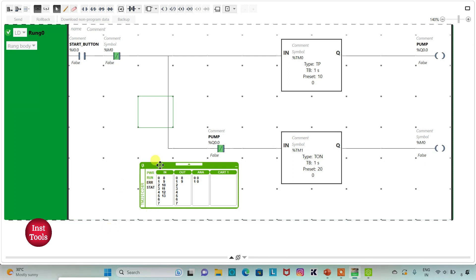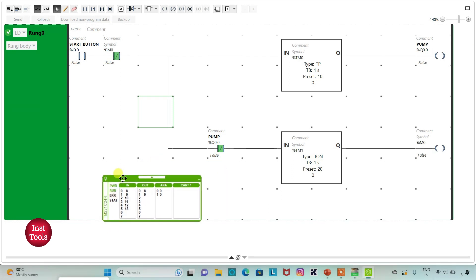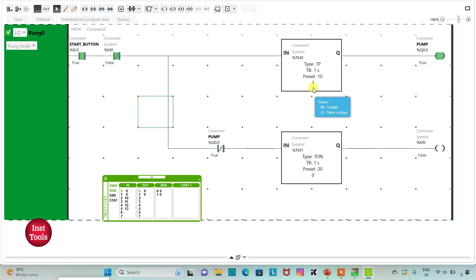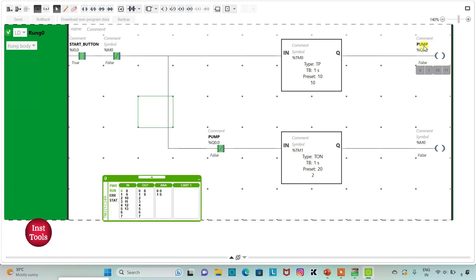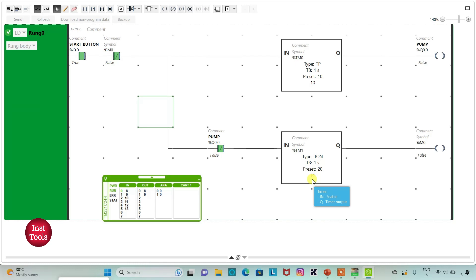So when I turn on start button, that is %I0.0, pump gets on for 10 seconds. Pump gets on for 10 seconds: 2, 3, 4, 5, 6, 7, 8, 9, 10. And after 10 seconds, pump gets turned off.